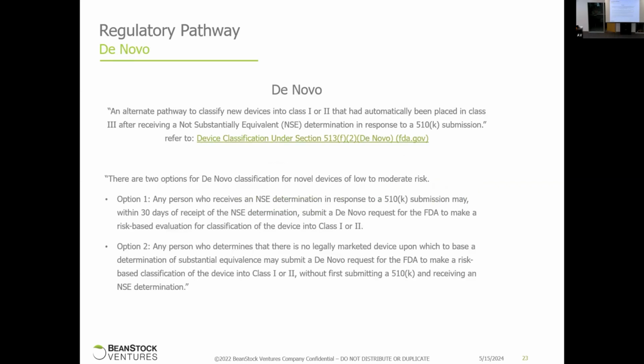De novo, this is probably, I would say, the most complicated one to define. It's basically if you're not class 1 or class 2 and you would go through PMA but you're lower risk than what FDA identifies as the high risk class 3 devices, then they'll put you in this de novo category. And so the requirements are a little bit looser, or lighter, I would say, than the PMA, but they're much more stringent than the 510K. So it's kind of like this unknown area between the PMA and the 510K. It's like, we're not a 510K, but we're not that high risk to be considered a PMA.